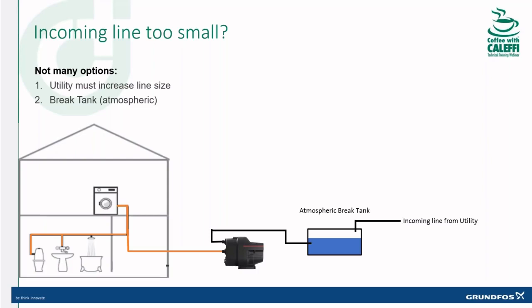A bigger pump can only do so much. It can't pull the same higher volume of water. So option A, the utility has to come out and increase the line size, or option B, you could do an atmospheric break tank. And that would provide the necessary volume of water, sized for your morning, noon, and dinner time spikes. But the problem is, it's atmospheric, so you lose all pressure from the city and the pump has to reboost 100% of what you're looking for.